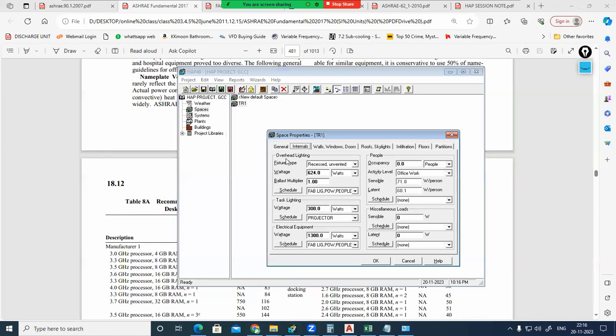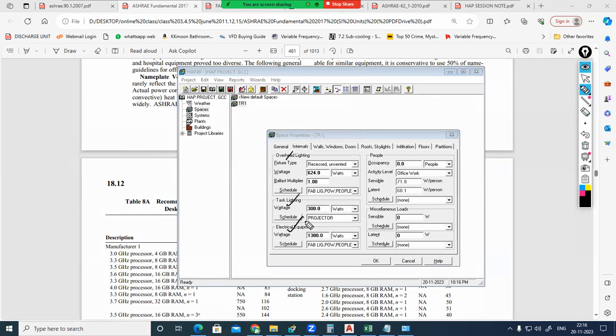Okay. Overhead lighting, task lighting, electrical equipment. Now people. See, all the heat gain that we have discussed now: overhead lighting, task lighting, electrical equipment. Is it sensible or latent heat? Whenever we are dealing with moist air or moisture or humidity, there should be latent, right? But light fitting is not producing any humidity. Task lighting is not producing any humidity. Electrical equipment is not producing any humidity. Kitchen equipment will come, I will explain that within the table. That is conditional. Correct. So that's why all these three are sensible only.